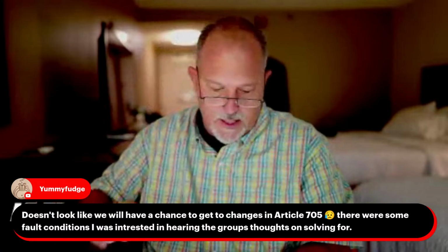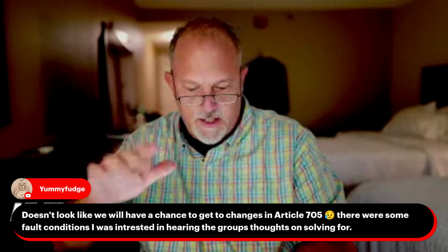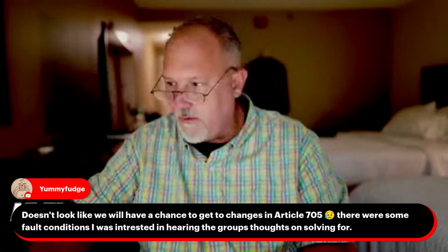Okay, let's talk about 705. I'm just looking. Surge protection is getting some changes. They added areas designed for use exclusively for sleeping quarters and fire stations. Service disconnect, readily accessible. We're requiring the service disconnect on the outside of the house now. So we deleted the emergency disconnect section because we're requiring the service disconnect for 1 and 2 family dwellings to be outside of the house. And so then we had to modify the marking requirements for the service disconnect, because it will be your emergency disconnect as well. We made some changes in the 2 to 6 service disconnect and all that jazz, but that's okay.